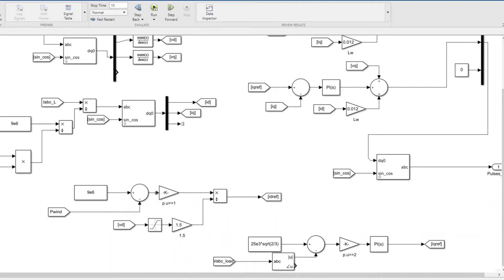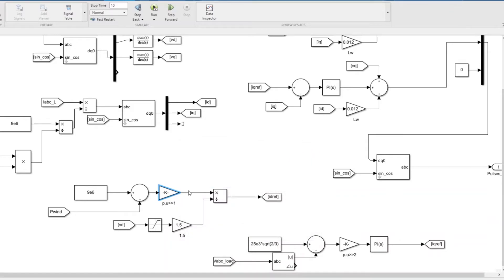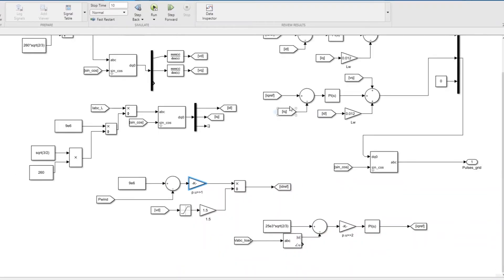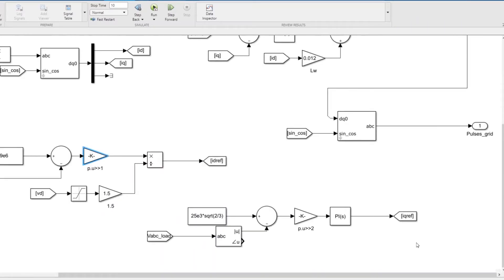This gives how much battery has to inject. I'm dividing it by 9 megawatts to get the number in per unit. You'll get the power in per unit, and dividing by 3 by 2 times vd will give you the current reference. This is the reference current the system has to inject to provide the required power, giving you the d-axis current reference.